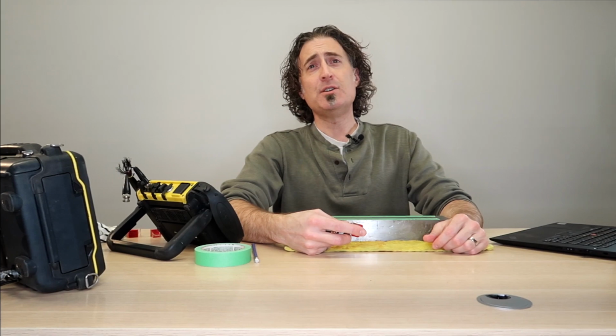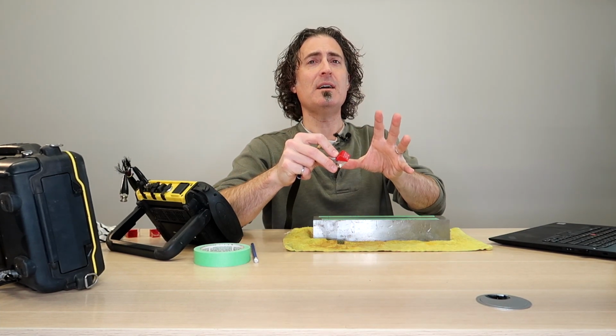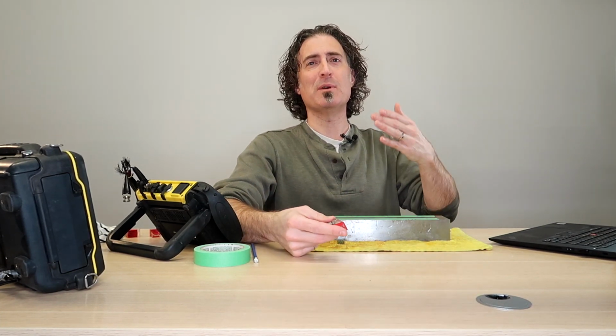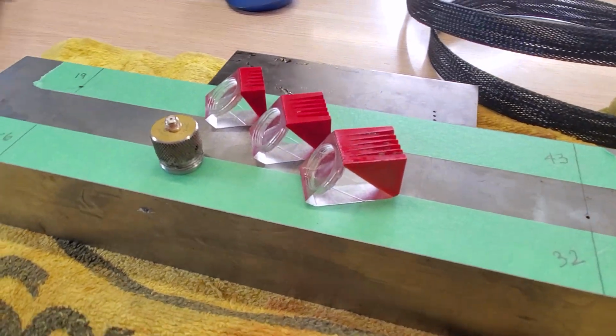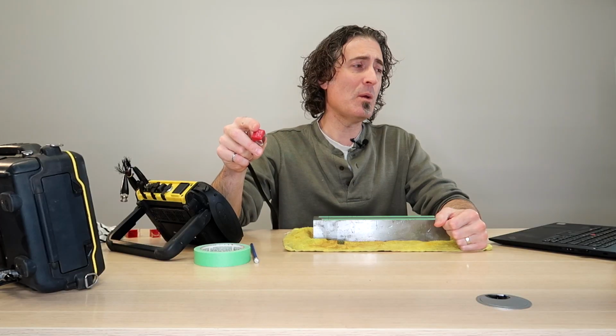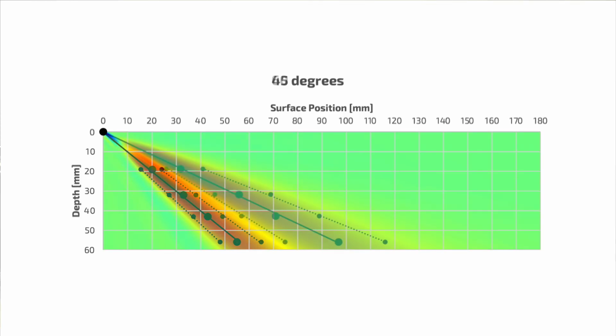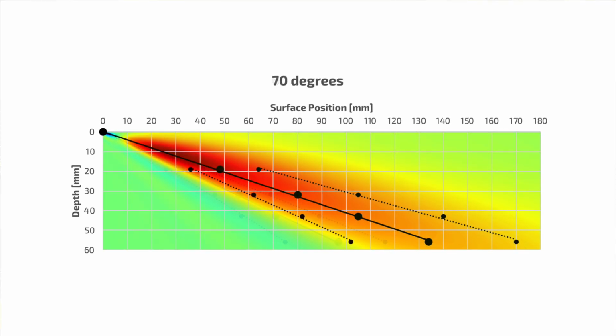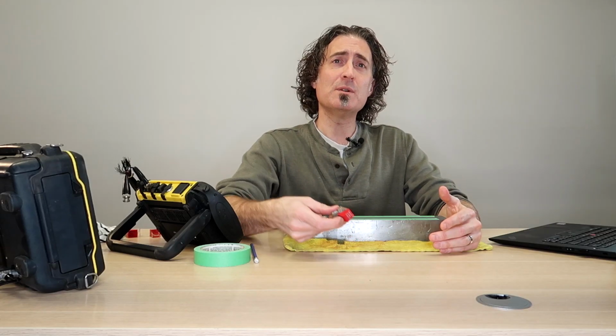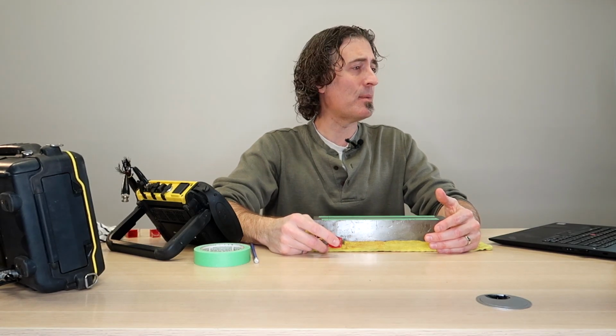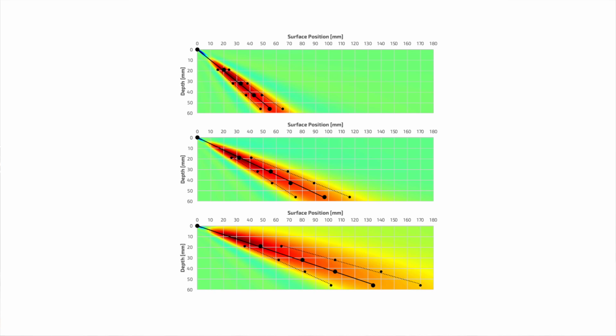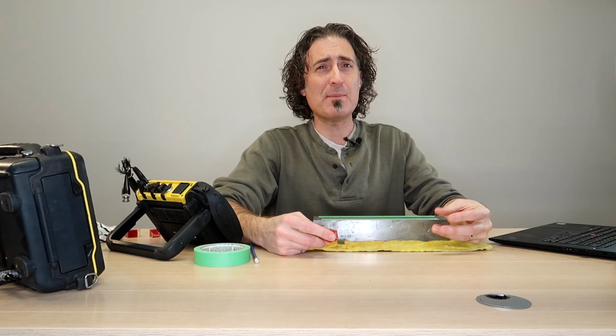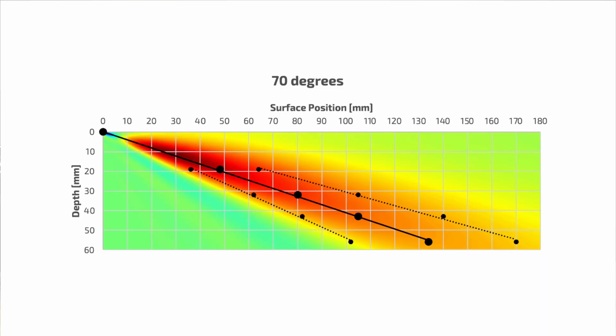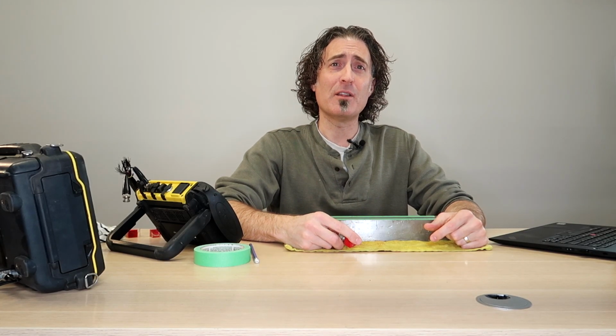Points just below the surface, maybe in the near zone, and the near zone tends to be a little bit wonky. I chose a 2¼ meg transducer over a 5 just because it's a lower frequency, a little bit more beam spread, a little something more to look at. When we plot the 45-degree wedge and the 70-degree wedge, just look at how much the beam spread changes over angle. So even though it's the same size of transducer, and all we did was change the incidence angle at the top, that's due to something called effective aperture. That effective aperture drops at 70 degrees. That's why it gets so wide and messy. I'm going to talk about effective aperture on another video.